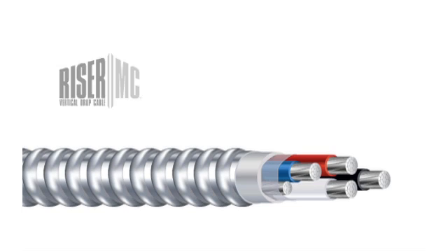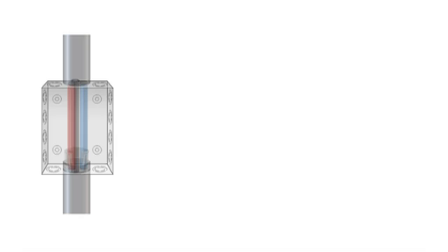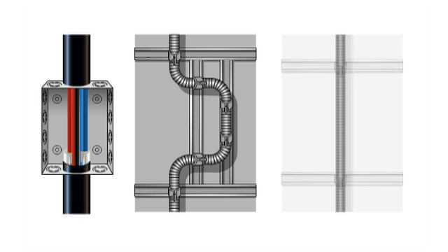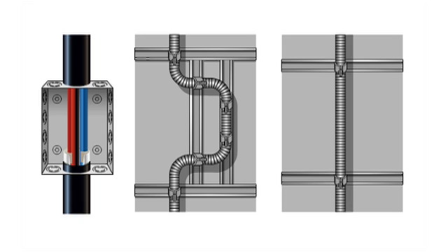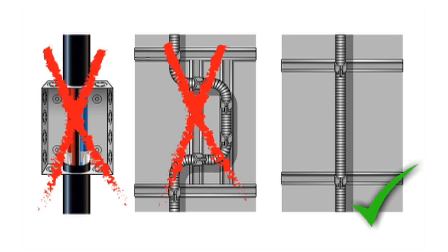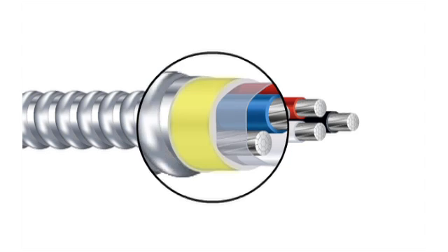Southwire has developed an alternative product that provides the most efficient solution for commercial vertical installations over ten stories: patent-pending riser MC cable. Using riser MC cable eliminates the need for any type of special conductor supports or offsets because of the internal polymeric binder underneath the armor that holds the conductors in place. On high-rise residential and commercial jobs that require larger feeder cables, it becomes labor-intensive to install offsets or conductor supports.